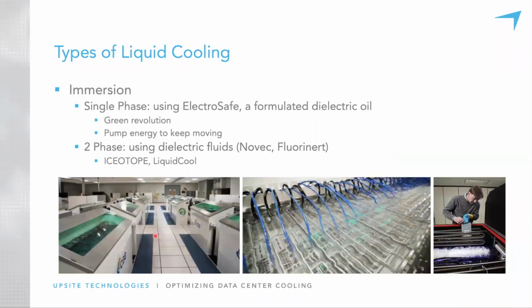Here's some images of the immersion cooling. There's a number of different providers out there using a number of different fluids, such as Novec or Fluorinert. And obviously, we have tanks now, basically a cabinet on its side, and all the equipment sits in the vat of liquid. There's single phase and two phase. Two phase means that the liquid boils off, becomes a gas, and then condenses again back to a liquid. And there's single phase, which just stays a liquid the entire time.